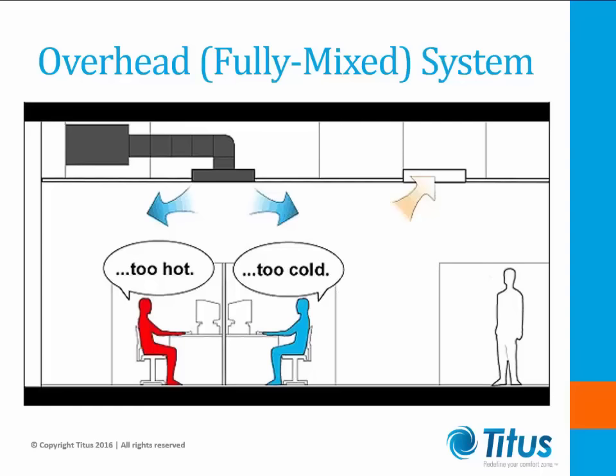Systems that deliver air from overhead typically supply cooling at 55 degrees Fahrenheit. This is necessary because in order to deliver cooling to the occupied zone and ventilation to the breathing zone, the supply air must first break through the layer of warm air at the ceiling. This layer is formed due to the increased buoyancy of warmer room air, often containing higher concentrations of pollutants and contaminants, and the heat from lighting systems. Since people often have different preferences when it comes to thermal comfort, it can be challenging to keep everyone satisfied and productive when spaces are served by a single thermostat setting. UFAD systems are different.